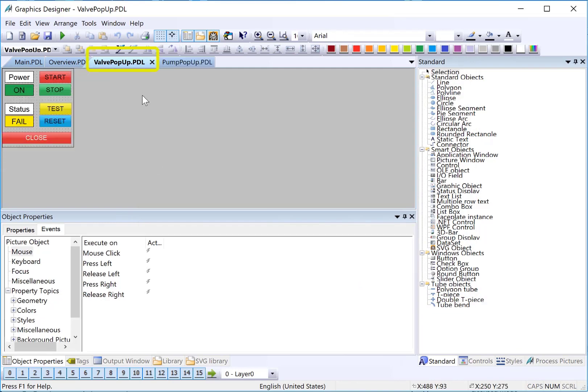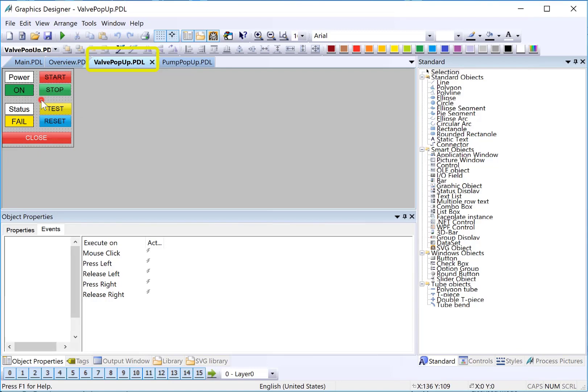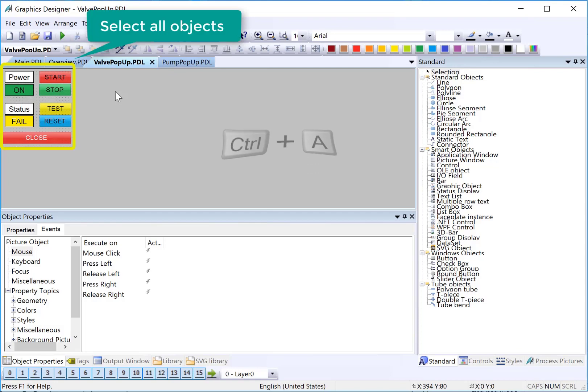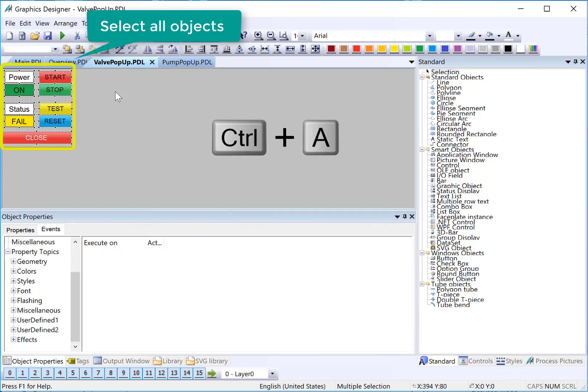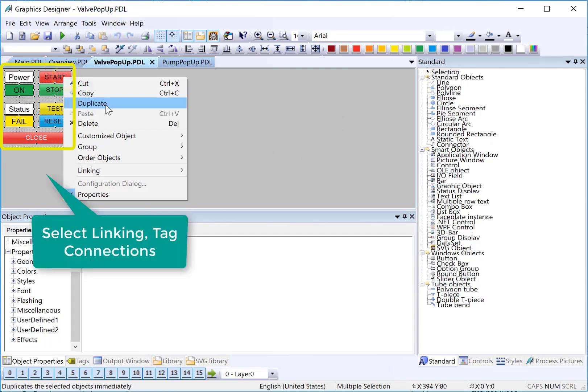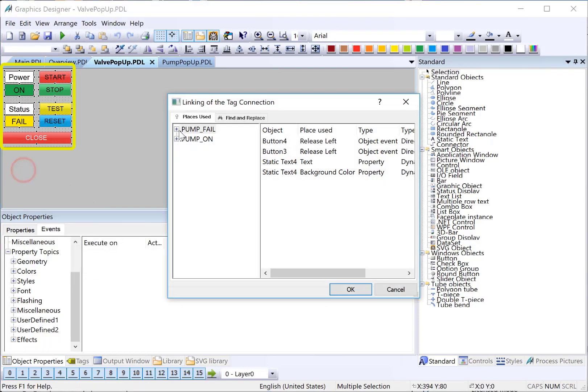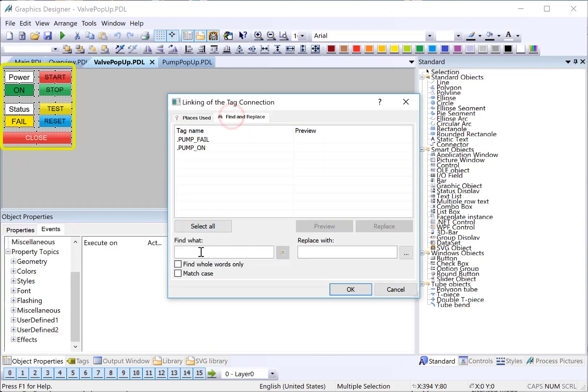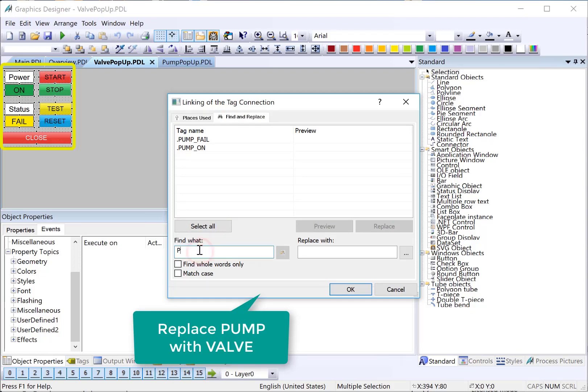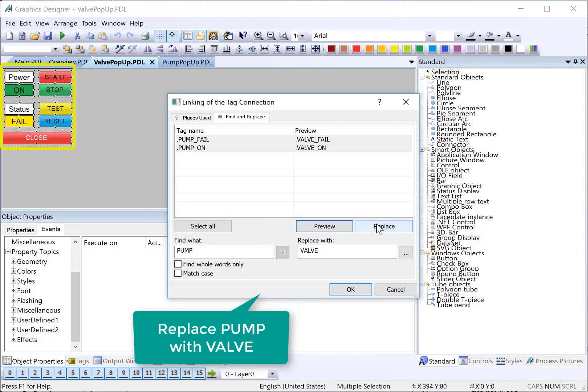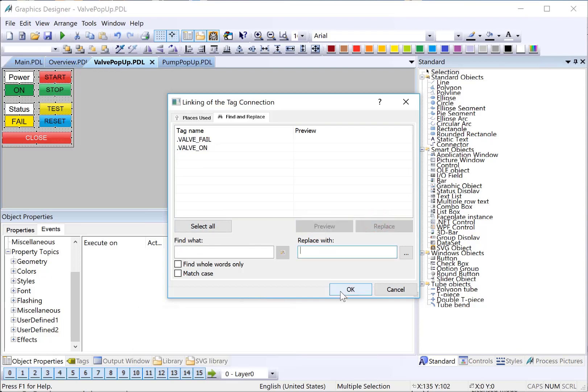Now we need to add dynamics to our valve pop-up. We need to change all of our pump tags to valve tags. And then we have some text that need to be changed. We can use our linking tool to do search and replace to make this go a lot faster. I'm just going to select every object on the page using control-A. And then I'll put my cursor over one of the selected objects and choose linking tag connections. You can see that we have all the pump-on tags. So, I'll go to find and replace and just say find pump and replace it with valve. Make sure you spell it right and that the case is okay. I select these and do preview and then hit replace.